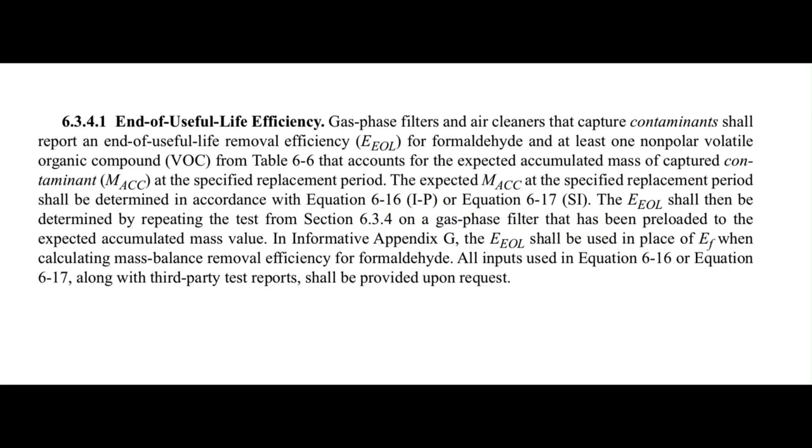The next aspect of air cleaner selection as required by the standard is to evaluate how long the filter will hold up in the application, and therefore you need to evaluate the end of useful life efficiency of that filter. This is only applicable to gas phase filters, and you're going to look at how well it holds up against formaldehyde and one other nonpolar volatile organic compound. And you will rate your air cleaner's performance at the end of life for that filter.